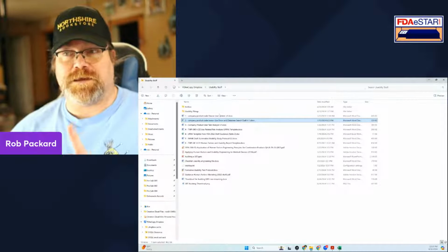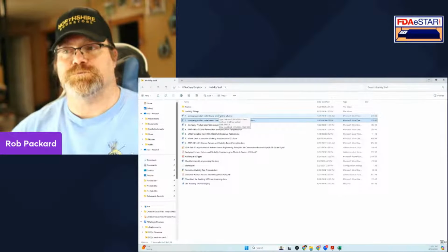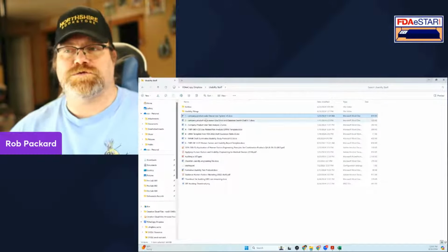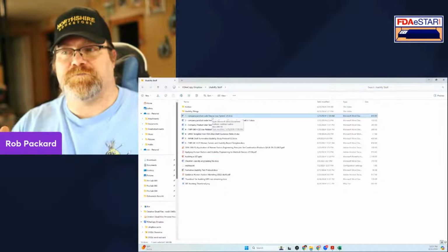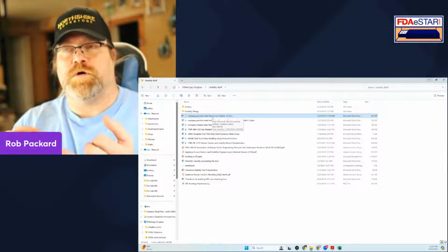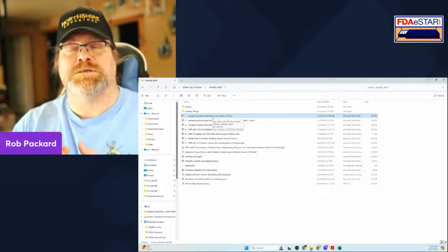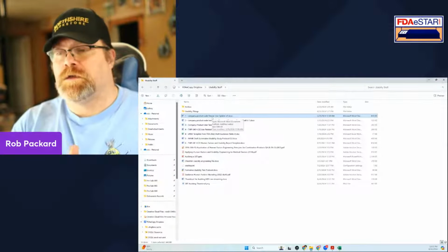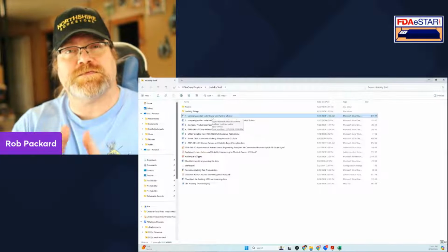And then last but not least, because I've been working backwards to the very beginning, the first thing you should be doing is identifying use specifications. And we use the name that the FDA came up with, the product device user system. So what they want is the indications for use. They want the intended use environment, the intended patient population, the intended user groups, and the device user interface.